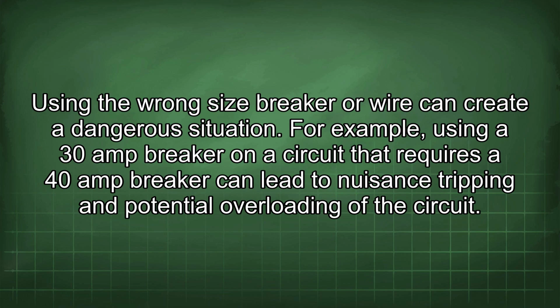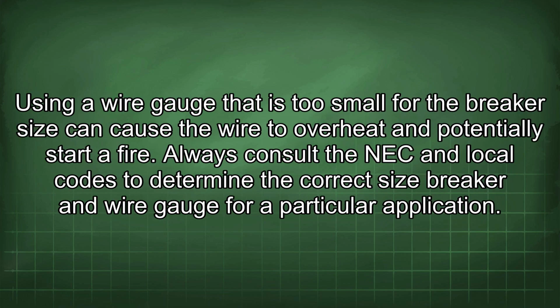For example, using a 30 amp breaker on a circuit that requires a 40 amp breaker can lead to nuisance tripping and potential overloading of the circuit. Using a wire gauge that is too small for the breaker size can cause the wire to overheat and potentially start a fire.